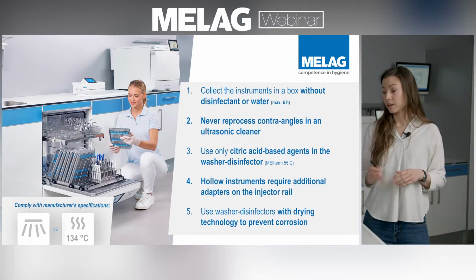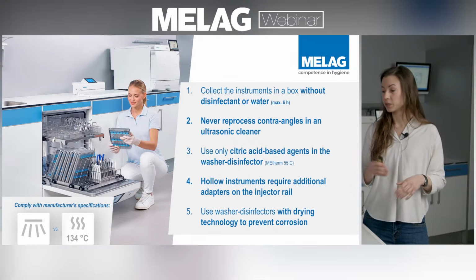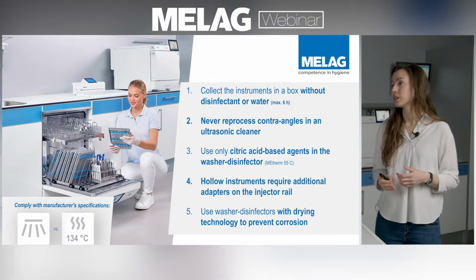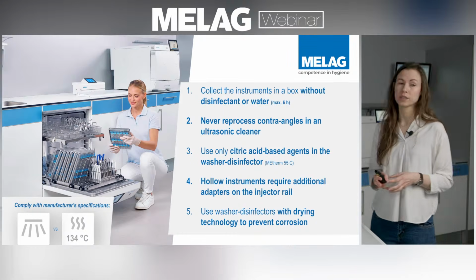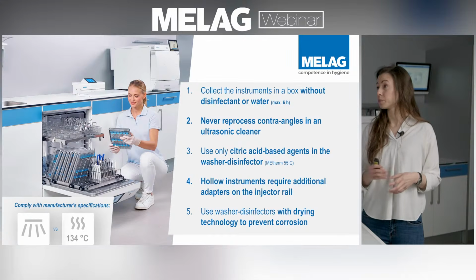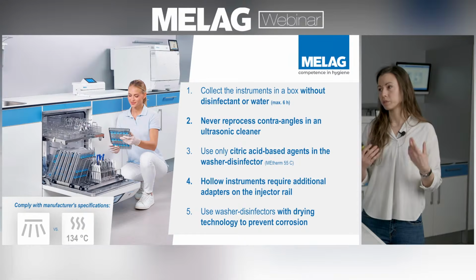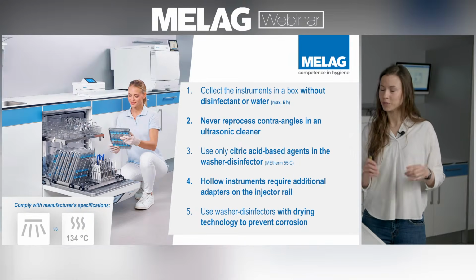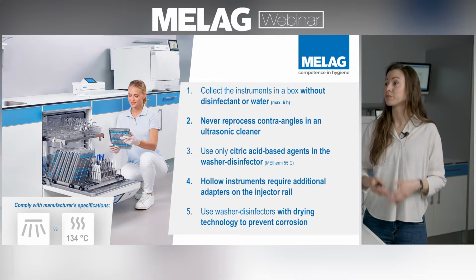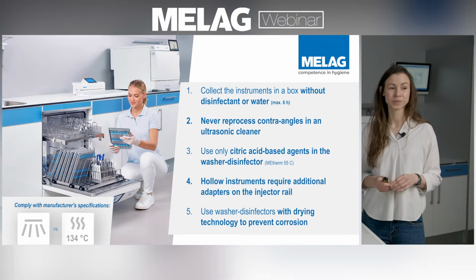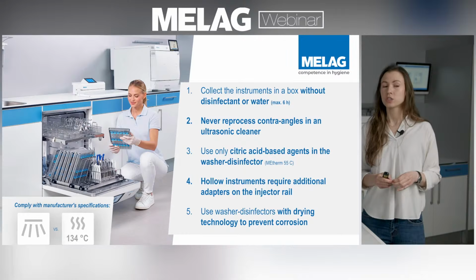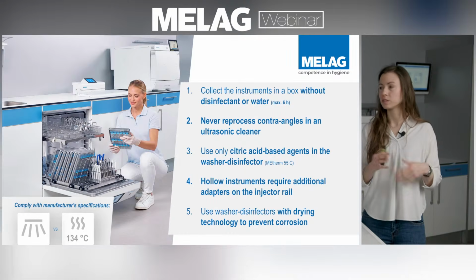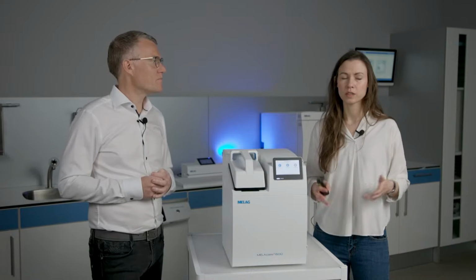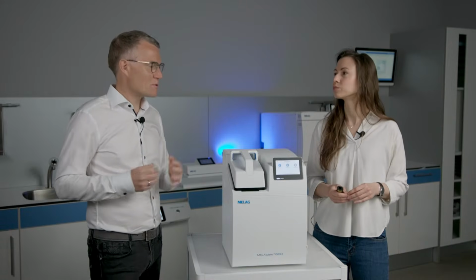And of course, if you put them in a thermal disinfector or any reprocessing device, it's also important that they are connected correctly. There are different adapters available depending on the type of instrument that you use, which ensure that water not only gets splashed on from the outside, but also runs through the inside of the instrument, cleaning it really well. And as a last step, it is recommended to use dry technology, meaning a device with a drying function, to prevent any type of corrosion. Makes absolute sense. Yes. Right.